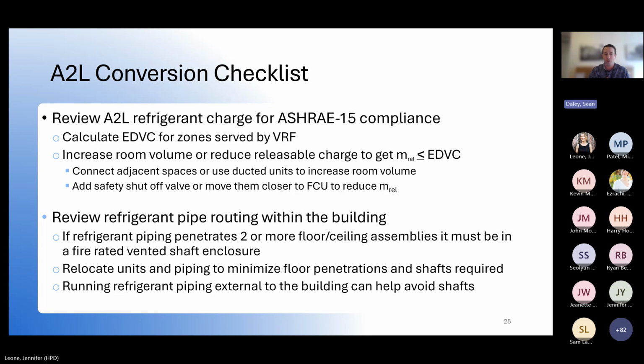The other main focus point, other than refrigerant charge, is pipe routing. We touched on this before with the fire-rated ventilated shafts. If refrigerant piping penetrates 2 or more floor ceiling assemblies, it must be in a fire-rated vented shaft enclosure. Two or more floor ceiling assemblies is not much, especially in the New York City multifamily market. So that's going to be a big hurdle for us. If you can, relocate the unit's piping to minimize floor penetrations and your shaft requirement.